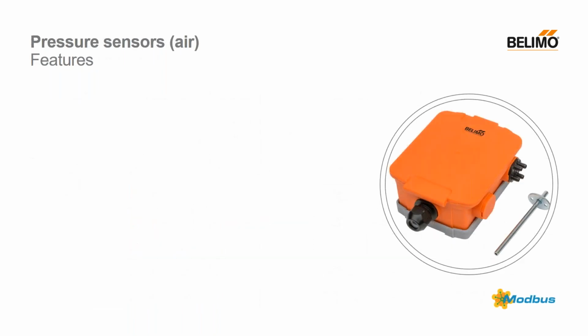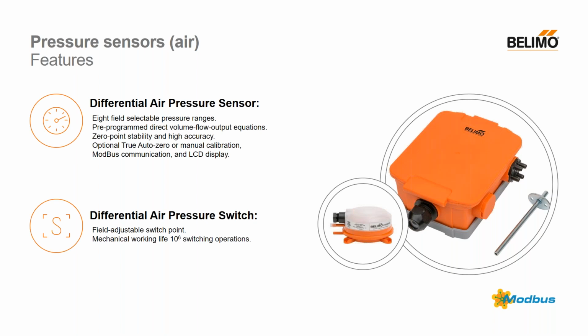Another area we have developed is pressure sensors for the air side of the business. Of course, the most important thing in most variable airflow systems is going to be the DP sensor. The DP sensor is an accurate sensor with selectable output ranges and about a 0.8 to 4 second response time, which is adjustable. When I say accuracy, we're plus or minus 0.2 inches of water column below 2 inches of water column, and above 2 inches of water column measured differential, we are plus or minus 0.4 inches of water column accuracy.